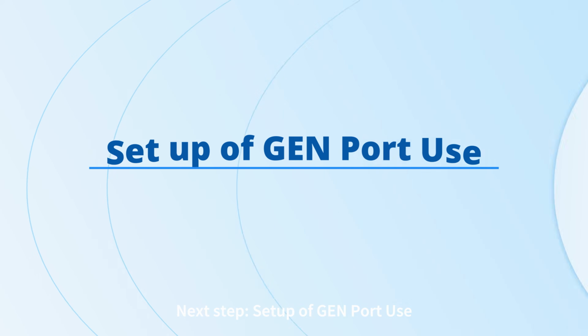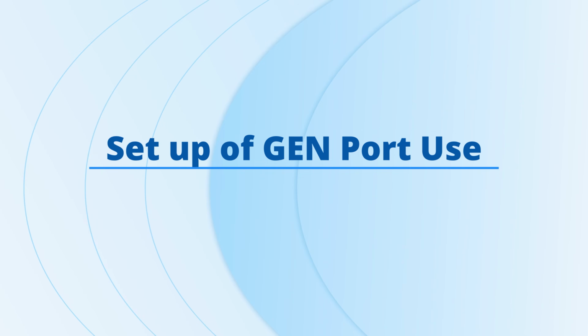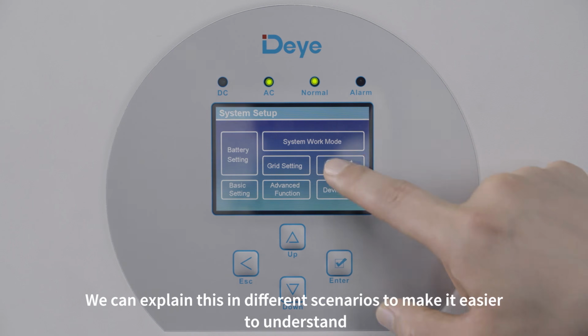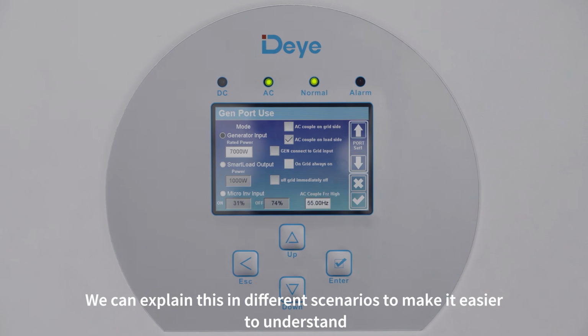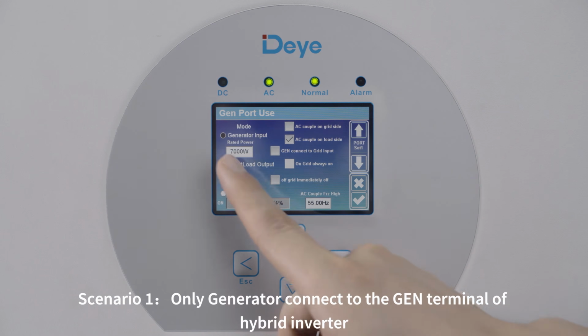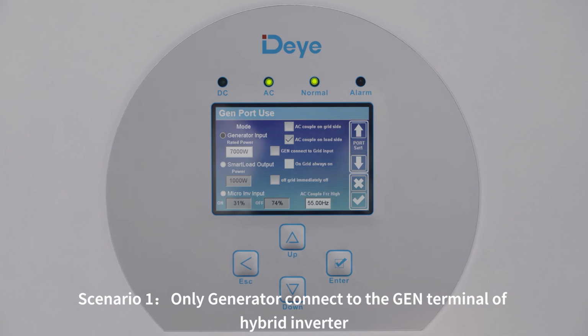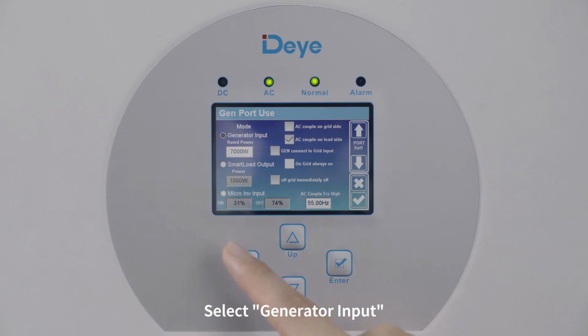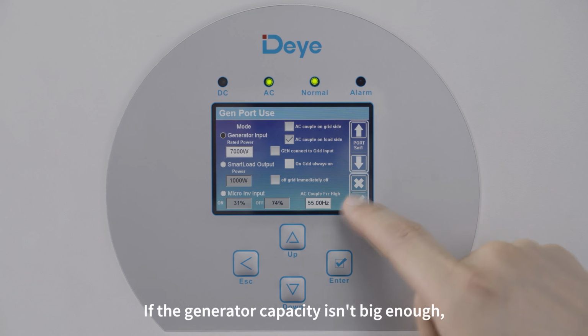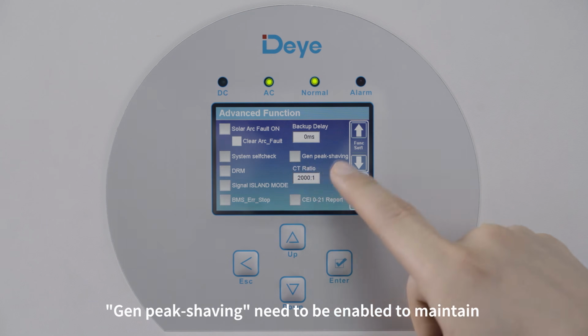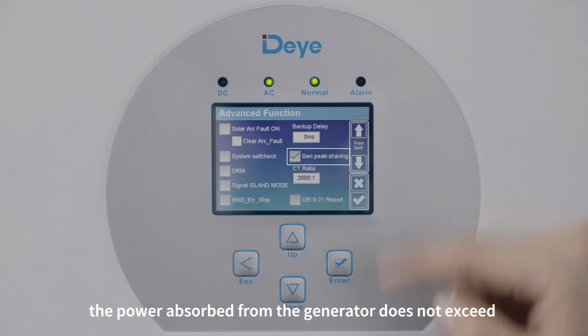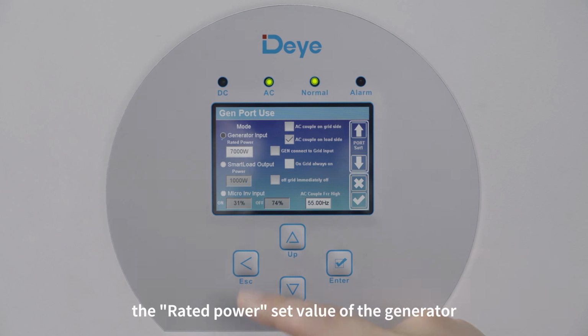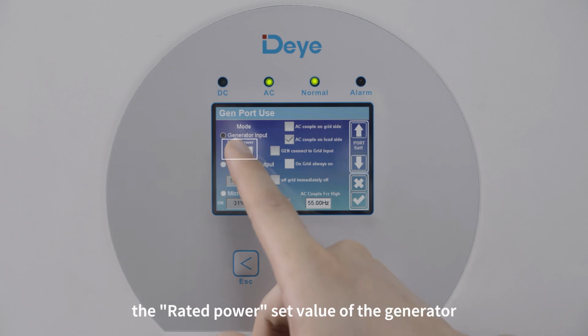Next step, setup of GEN port use. We can explain this in different scenarios to make it easier to understand. Scenario 1. Only a generator is connected to the GEN terminal of the hybrid inverter. Select generator input. If the generator capacity isn't big enough, gen peak shaving needs to be enabled to ensure the power absorbed from the generator does not exceed the rated power set value of the generator.